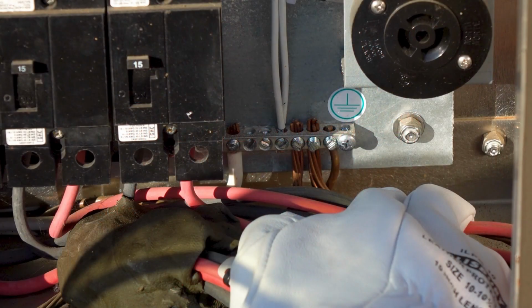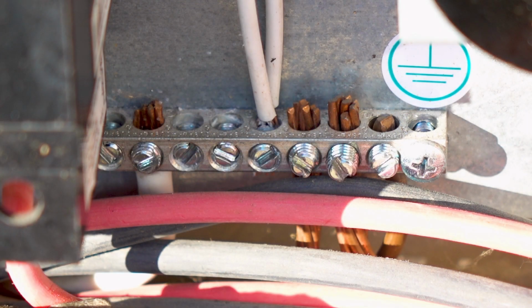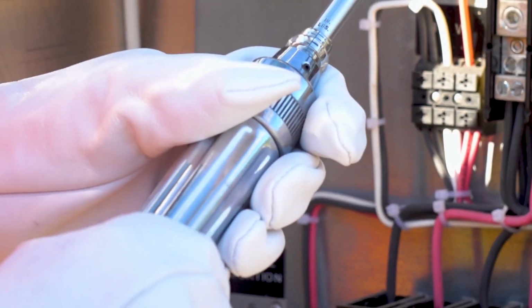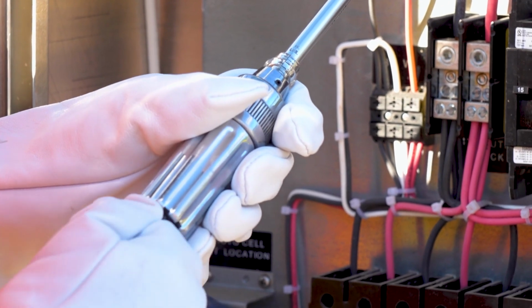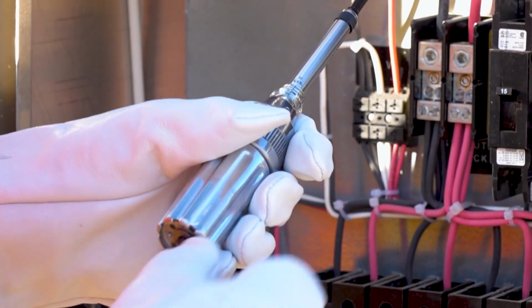The inspector will need to visually examine each conductor connected to the bus to verify that none of it has been nicked or had any strands cut off. If a conductor has nicked or cut strands at the termination to the bus bar, the connection must be rejected and remade by the installing contractor. The torque of the screw lugs should be verified on all electrical connections made by the installing contractor.